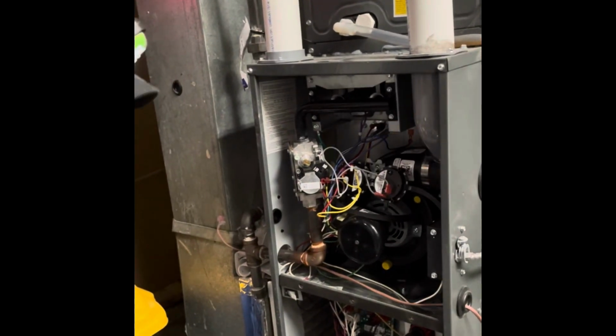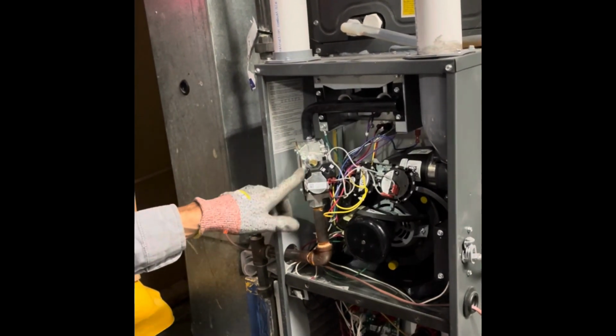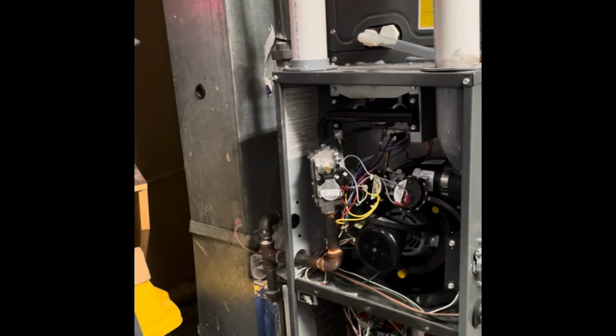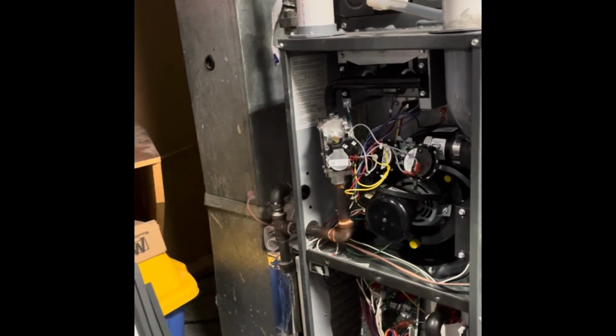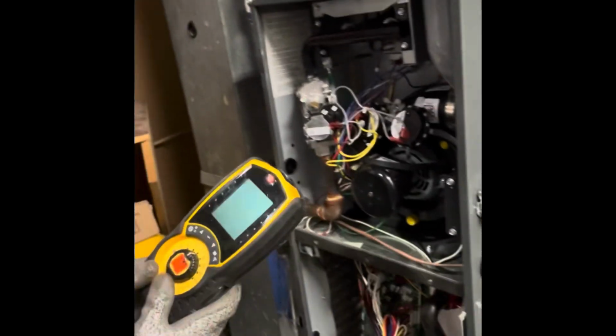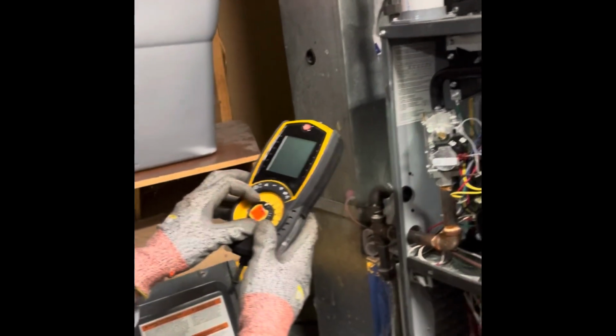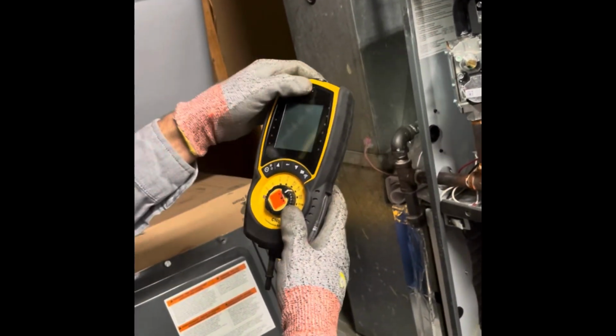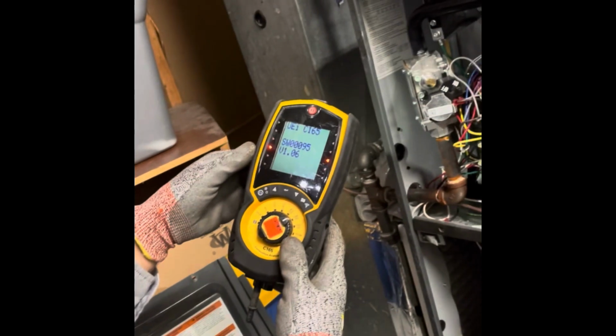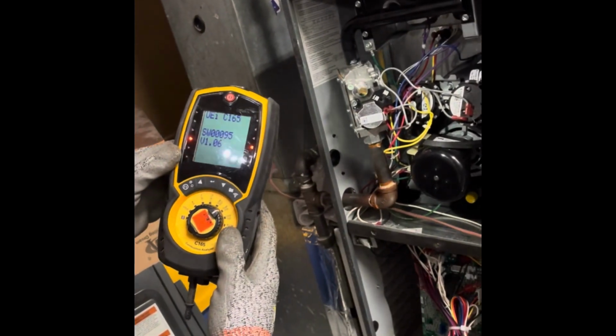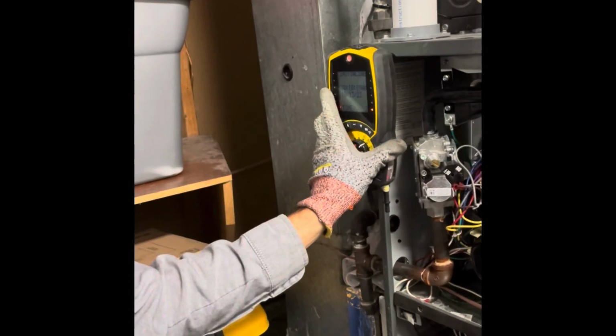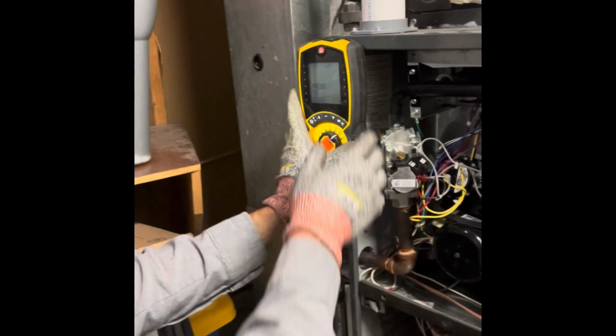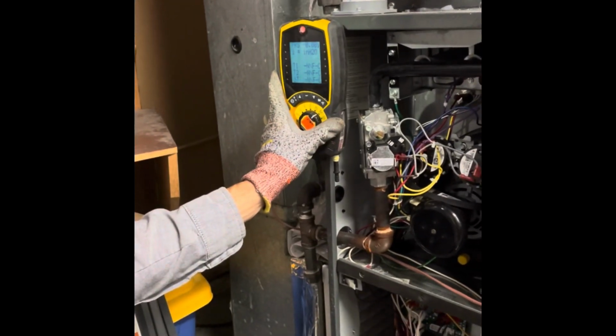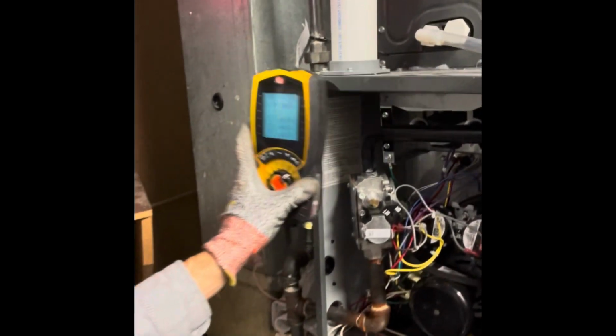So I'm going to hook up my manometer. I want to check pressure here. The measurement that we're going to be dealing in is inches of water column. And with this particular furnace, I'm aiming for 3.5 inches. So I'll turn my manometer on. This is also a combustion analyzer, which lets me check carbon monoxide in the exhaust as well as in the house. So we'll let that start up. Just zero that. So we're at 0 pressure right now.